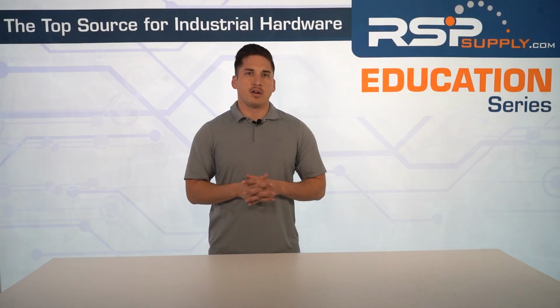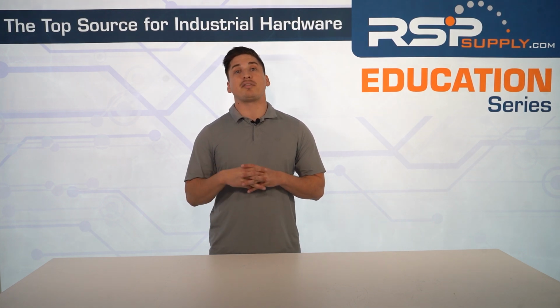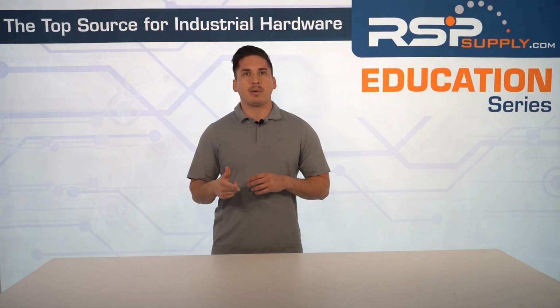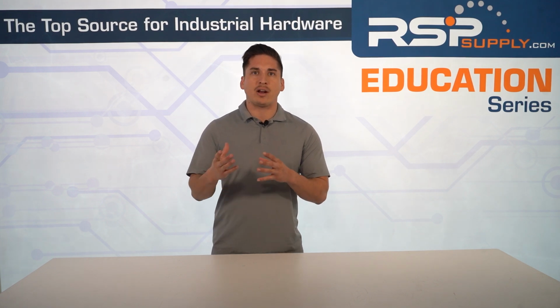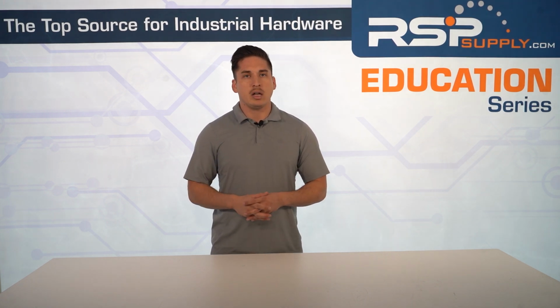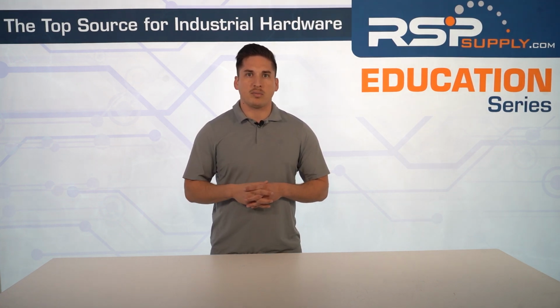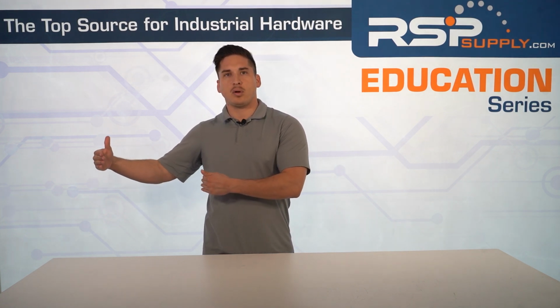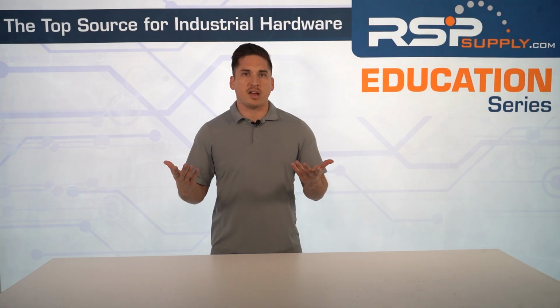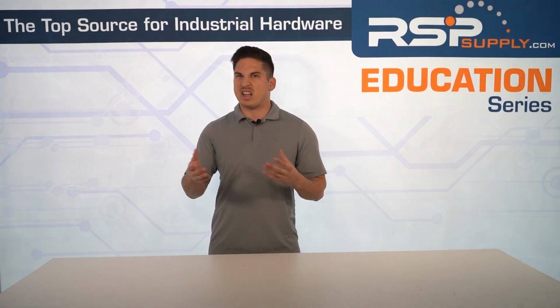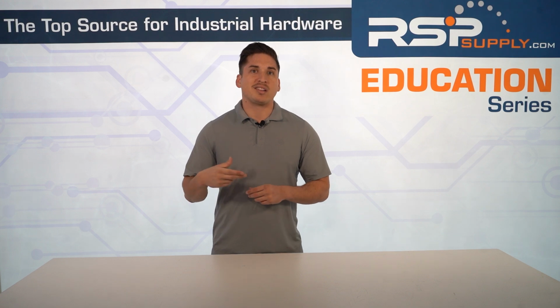Types of switchgear used. There are different types of switchgear, and it's categorized based on voltage, installation environment, and the medium used for insulation and arc interruption like we were just discussing. Categorizing them by voltage, there's obviously low voltage switchgear. That handles up to 1 kilovolt, used in small commercial and some residential systems. Medium voltage switchgear ranges from 1 kilovolt to 36 kilovolts. That's often found in industrial settings. Then you have your high voltage. That's where it's connected to the utility. That's above 36 kilovolts, used in utility and large-scale power distribution.